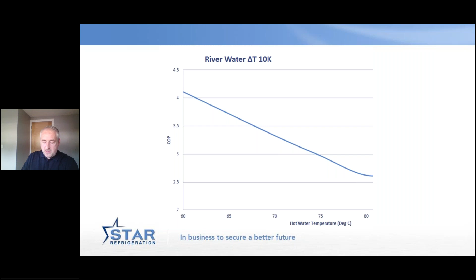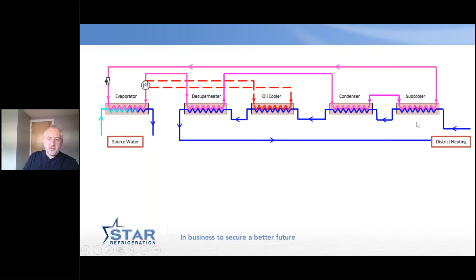So you can see there's a little bit of complexity here, although compared to Drammen, it's much simpler. We've just got one heat pump in each circuit, and they're not interposing with each other. And we've got the subcooler getting the first chance to raise the temperature of the return water, and then the condenser, then the oil cooler, and the desuperheater. So that's the main bulk of it.